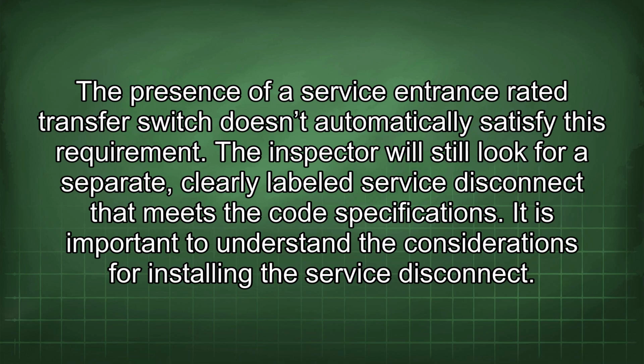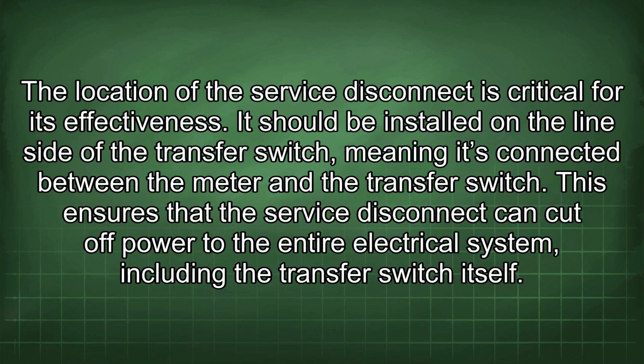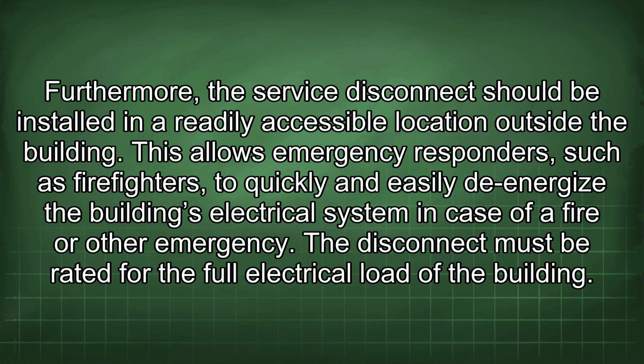It is important to understand the considerations for installing the service disconnect. The location of the service disconnect is critical for its effectiveness. It should be installed on the line side of the transfer switch, meaning it's connected between the meter and the transfer switch. This ensures that the service disconnect can cut off power to the entire electrical system, including the transfer switch itself. Furthermore, the service disconnect should be installed in a readily accessible location outside the building. This allows emergency responders, such as firefighters, to quickly and easily de-energize the building's electrical system in case of a fire or other emergency.